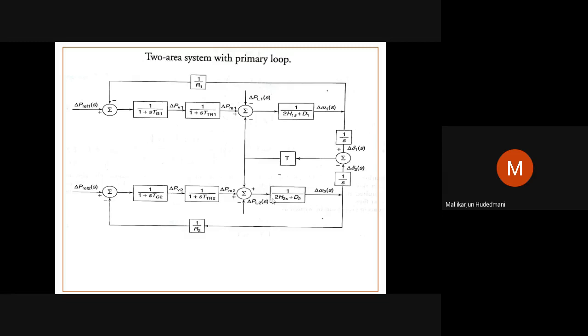Now the next concept is, when I say they are interconnected to one another, they must operate with a unique frequency omega only. Then the question comes, what is the value of delta omega 1, delta omega 2 at that time? They must try to balance a unique frequency. Imagine these two are far away from each other. They are not just beside each other in position. They are far away in geographical position. Definitely the frequency over here and the frequency over here need to be the same for interconnected operation. But due to the time plane, there will be a small lag. So that is how the change in this area's load is addressed by itself and by this. The change in this area's load is addressed by itself and by the neighbor through bidirectional control.